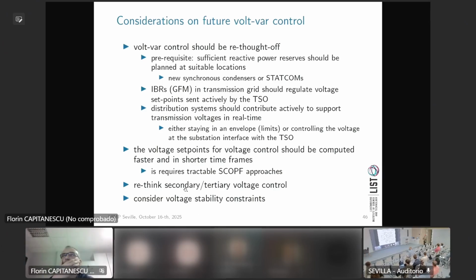And at the end of the day, it can do this reactive power provision. Probably it's much more difficult because in the case of a large power plant, you may have only a single unit that is quite easy to control. But in the case of a large PV plant, you have several PV inverters that you have to coordinate with a power plant controller. It is much more difficult, but I think that from the point of view of the quality of providing this reactive power to the system, it can be exactly the same. More tricky, but exactly the same. I would like your opinion on this.